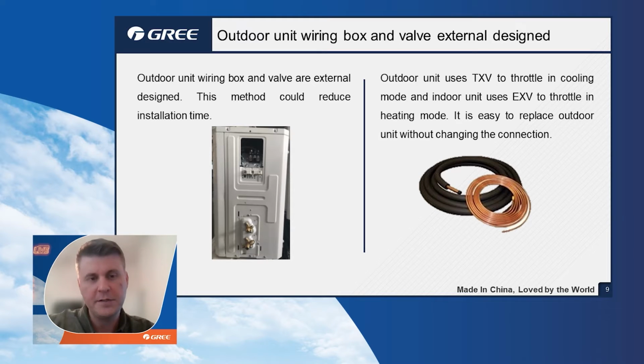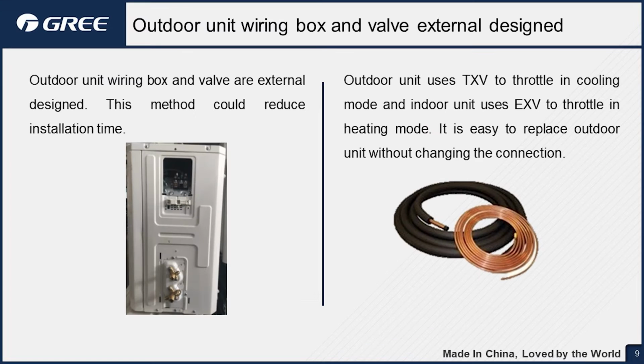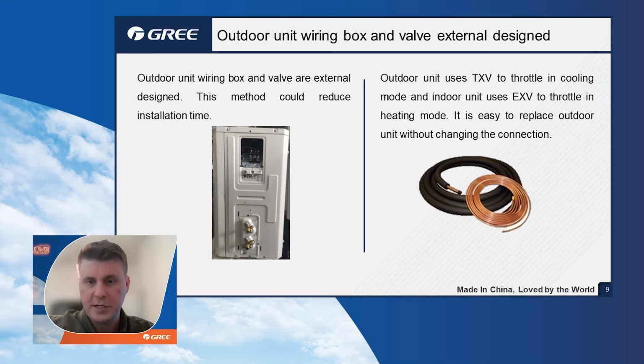On all the outdoor units, the valves are on the outside of the unit, and we've angled those at 45 degrees. With the original FLEXX on the 2/3-ton, the valves were actually up inside the unit, and it was very difficult to get to those—you'd have to use an adapter or get creative with your tubing benders. With this model, all the valves are on the outside, angled at 45 degrees, so you can get in there and connect to them quite easily.